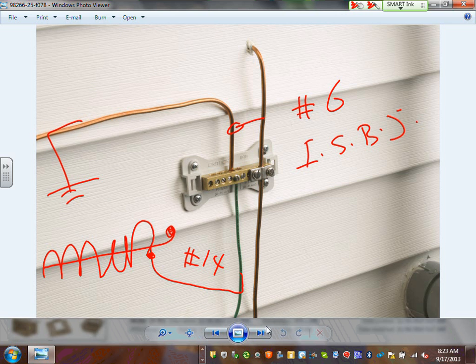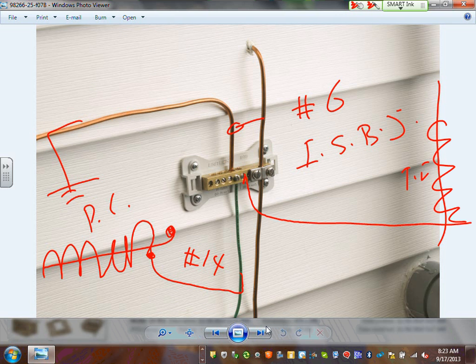So if I have a phone line here, and here's my shielded cable to the TV, you take the shield and ground it right here. This is the point where you ground the shield of all the low voltage systems. It's called the inter-system bonding jumper. It's required to be by the service, by the meter, wherever your service is located. You have to bond it to the grounding electrode system of your building.